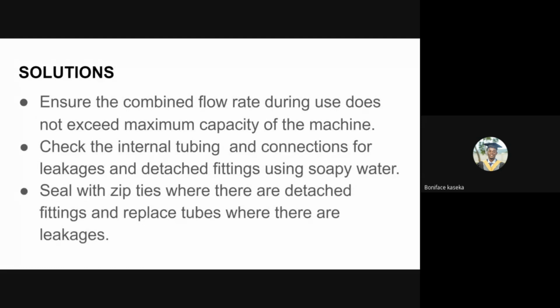First and foremost, you need to make sure that the combined flow rate during use does not exceed the maximum capacity of the machine. What we normally mean here is that if your total combined flow rate from the oxygen flow splitter is, for example, 8 liters per minute, but you are using an oxygen concentrator which has a maximum outlet of 5 liters per minute, then you are going to have a problem, because you are demanding more oxygen from the source than it is giving you. As a result you will have those fluctuations, because it won't be giving you 5 liters per minute when you actually need 8 liters per minute.